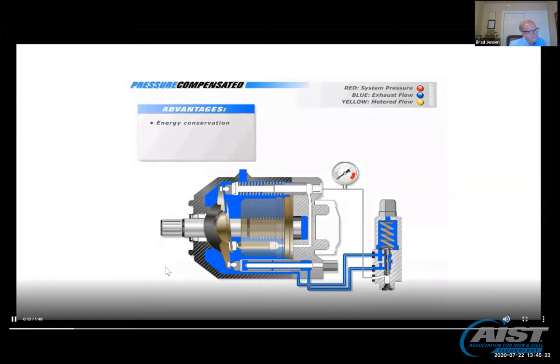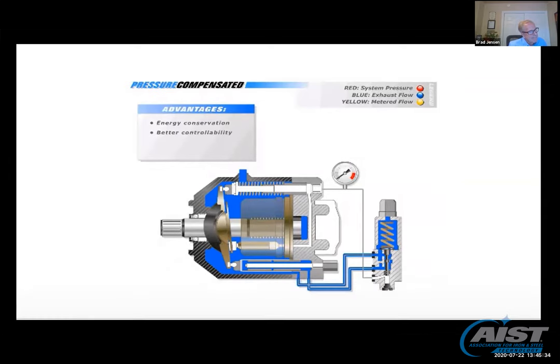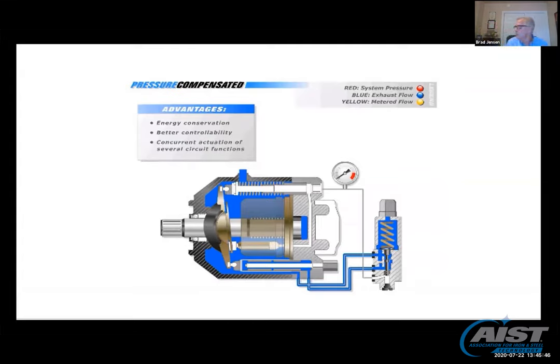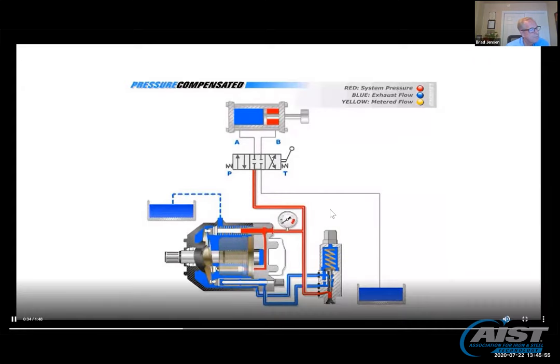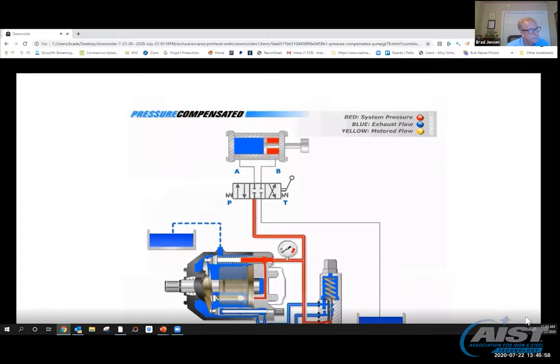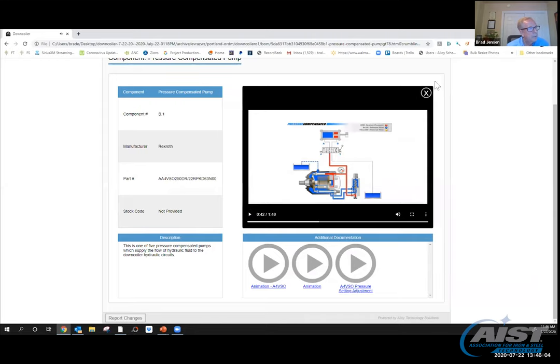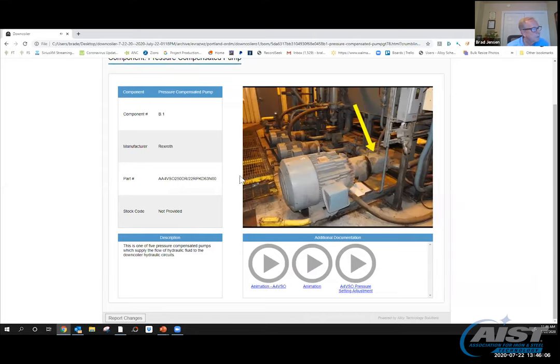This is the swash plate right here. These pistons and their shoes are riding on this as they go around and around. This spool up here—the spring has that swash plate at an angle. As long as that is at an angle, when this shaft is rotating, these pistons are going in and out. They're drawing fluid in on the suction side. When they start back down the swash plate, they're pushing it out. That's how we produce flow. When the pump goes into standby, this swash plate has to go perpendicular to the shaft. Advantages of a pressure compensated circuit are energy conservation, better controllability, and concurrent actuation of several circuit functions. Some advantages are offset by higher component costs.